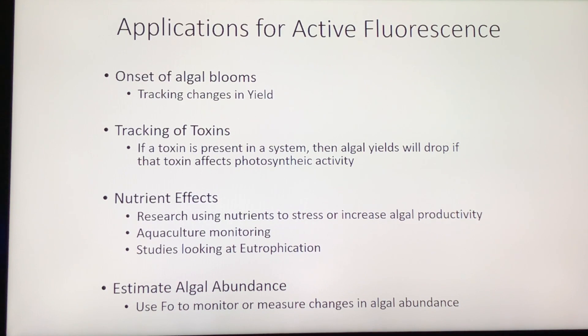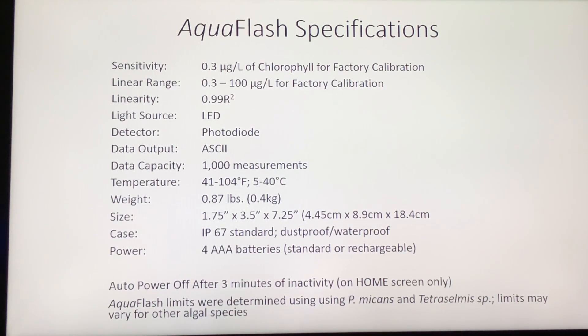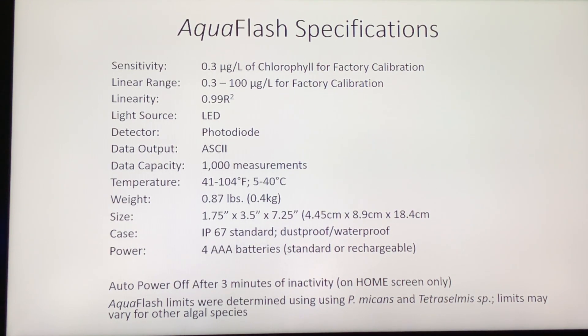Aquaflash also provides a good estimate for algal concentrations as micrograms per liter of chlorophyll. Aquaflash is sensitive down to 0.3 micrograms per liter of chlorophyll and can read up to a maximum of 100 micrograms per liter. These limits were determined using Prorocentrum and Tetraselmis cultures. Limits will vary with respect to species and physiology of algae, among other factors that influence in vivo fluorescence properties.